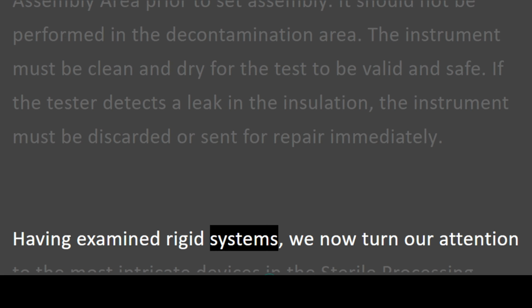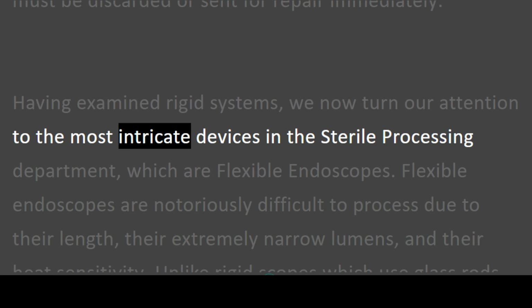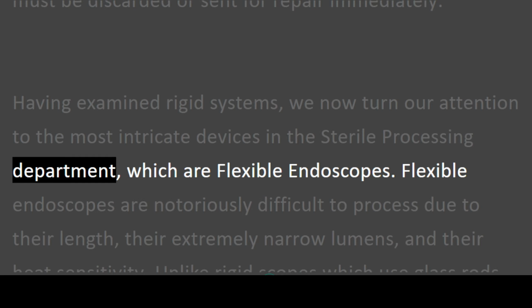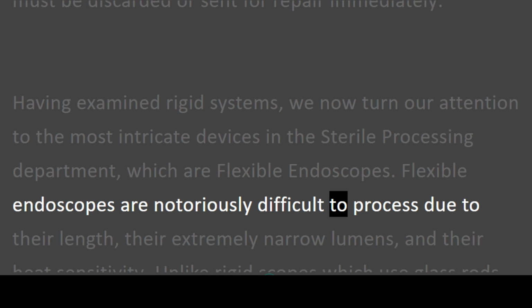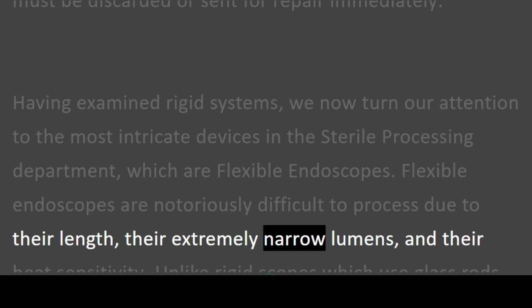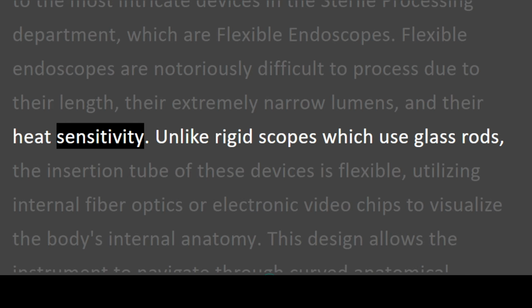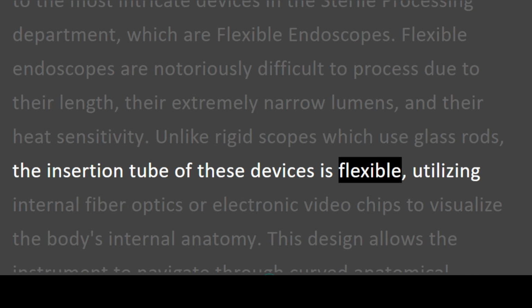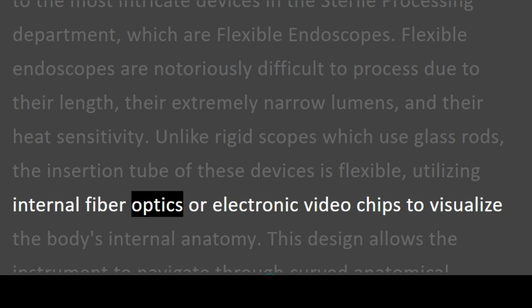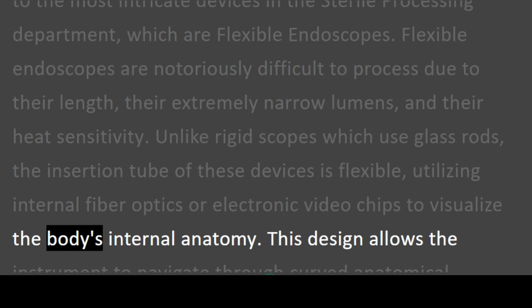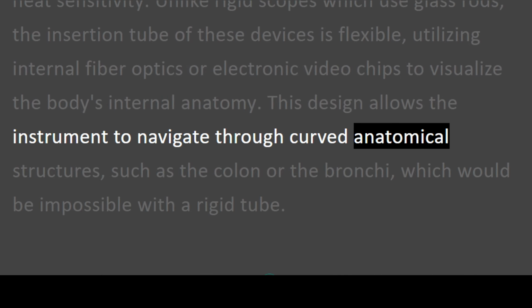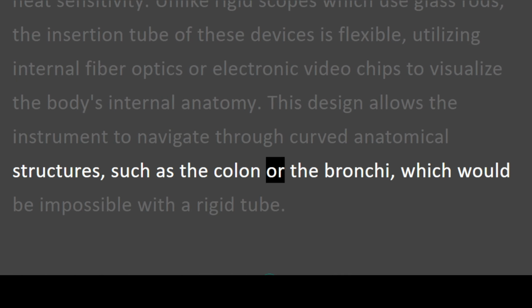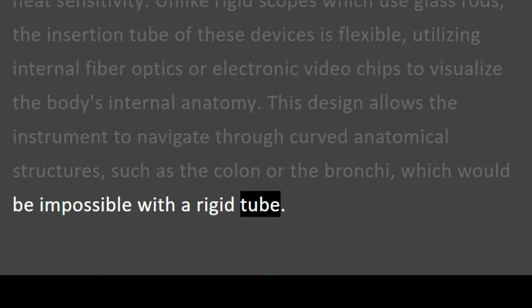Having examined rigid systems, we now turn our attention to the most intricate devices in the sterile processing department, which are flexible endoscopes. Flexible endoscopes are notoriously difficult to process due to their length, their extremely narrow lumens, and their heat sensitivity. Unlike rigid scopes which use glass rods, the insertion tube of these devices is flexible, utilizing internal fiber optics or electronic video chips to visualize the body's internal anatomy. This design allows the instrument to navigate through curved anatomical structures, such as the colon or the bronchi, which would be impossible with a rigid tube.